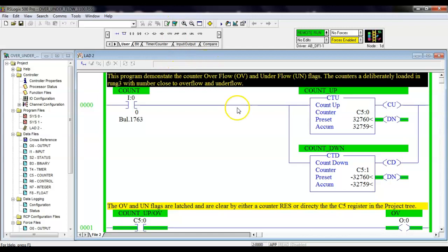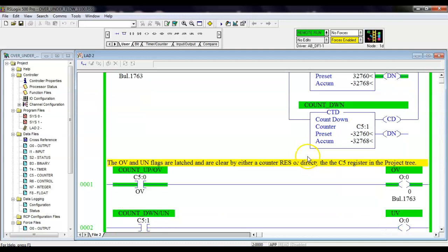What I'm going to do is come over and hit switch 0. And notice it's counting. 32,764, 5, 6, 60. Here we go. 32,767. Watch what happens to the sign. Went negative. And notice my overflow bit changed. So this would give an indication that I could monitor that overflow bit inside the status word and know when this happened. And what I'd probably do is start another count again.